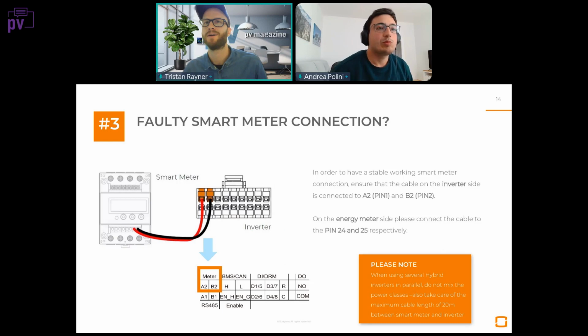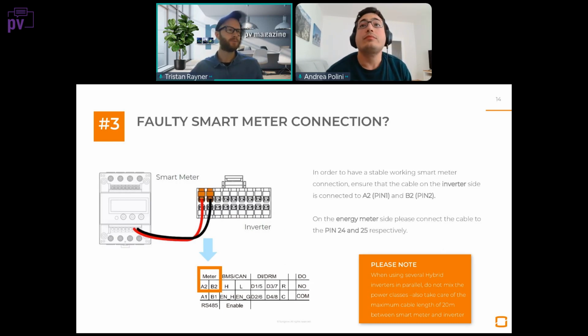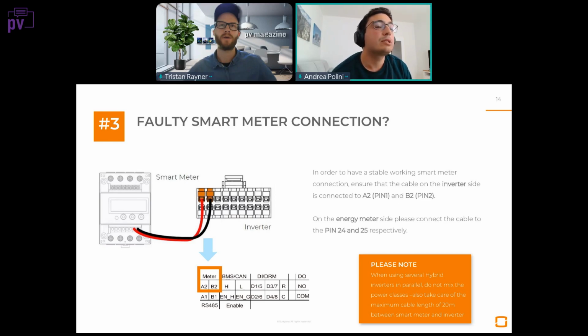Okay, no problem. Okay, with that done, let's move to our third most voted issue, which is faulty smart meter connection. Yes. One of the other items that usually makes some problems for our installers is how to properly connect the smart meter. So we supply the smart meter with our hybrid inverter in the package, whether it is the three-phase hybrid or the single-phase hybrid inverter. For our regular PV inverters, actually the installer must buy the smart meter as an accessory from our product portfolio from the distributor that they choose.